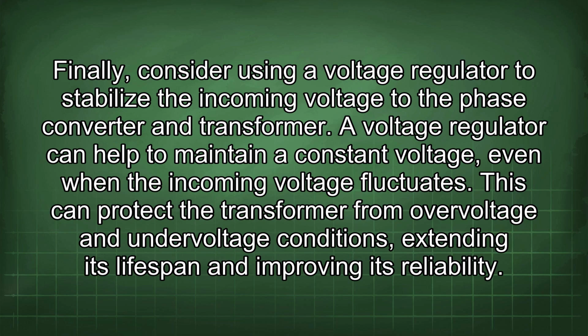Finally, consider using a voltage regulator to stabilize the incoming voltage to the phase converter and transformer. A voltage regulator can help to maintain a constant voltage even when the incoming voltage fluctuates. This can protect the transformer from overvoltage and undervoltage conditions, extending its lifespan and improving its reliability.